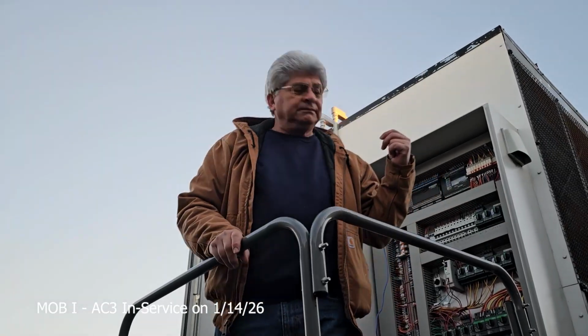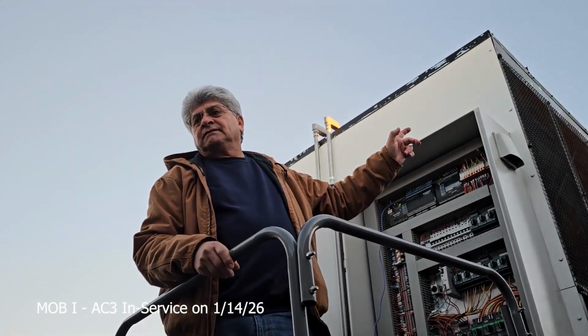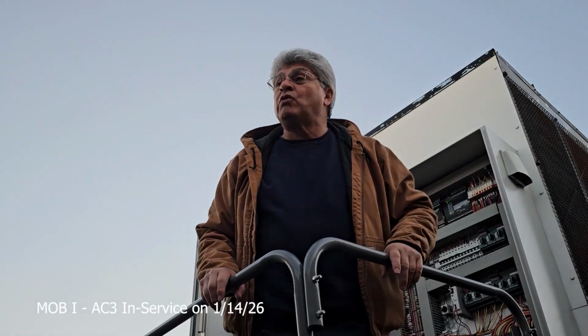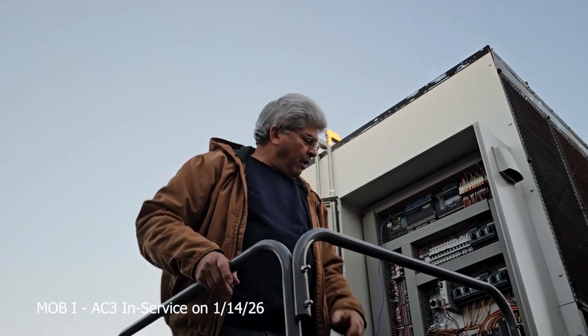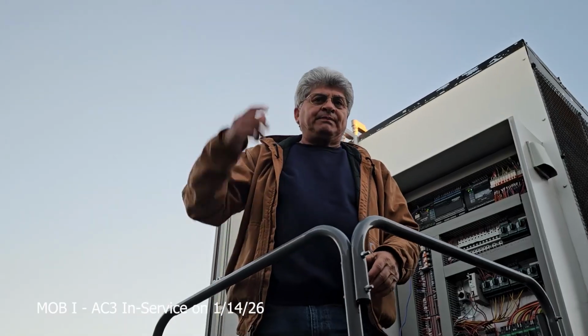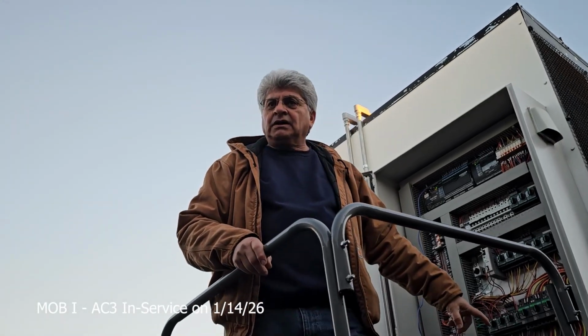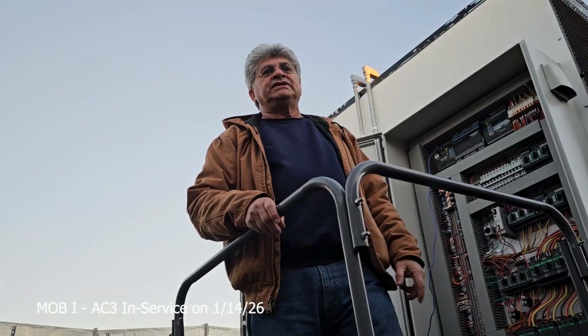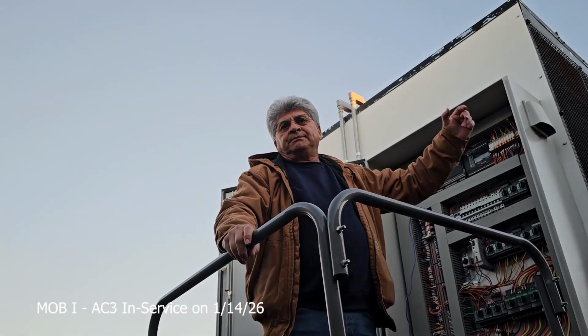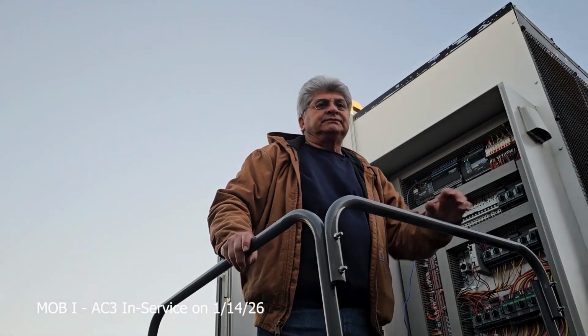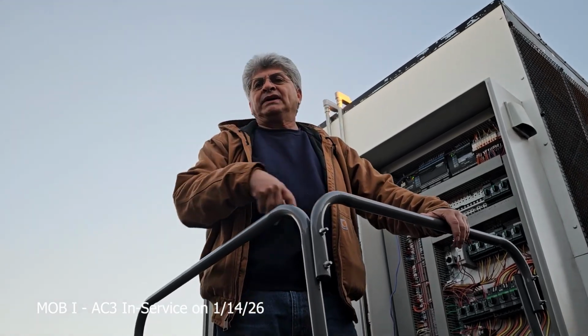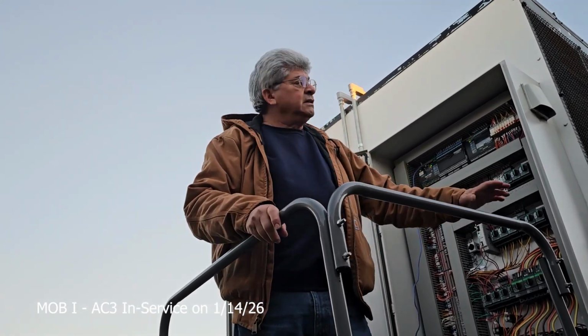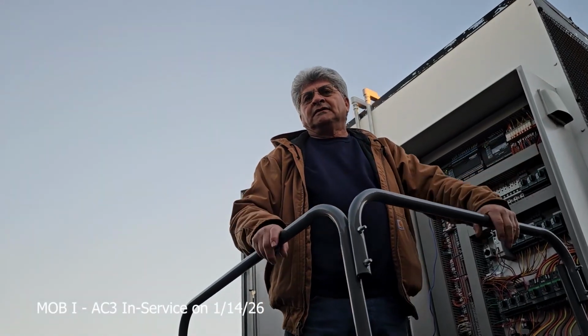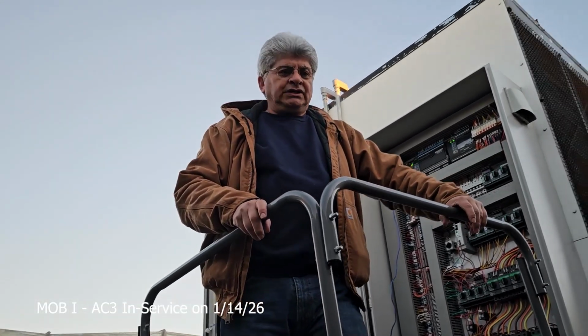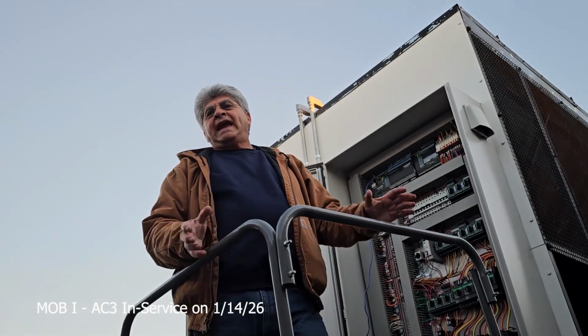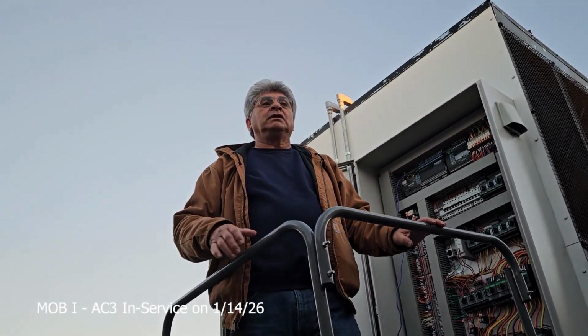If your controller, this locked up once while we were on site here. We were off site. They brought power in. They cranked power on, but they had the legs reversed, the phases. The controller locked up. Once they got that back on, he let it power down, did a master reset, and she came all back on her own. Nobody had to mess with it. It's pretty robust, but it can be sensitive to major power interruptions.